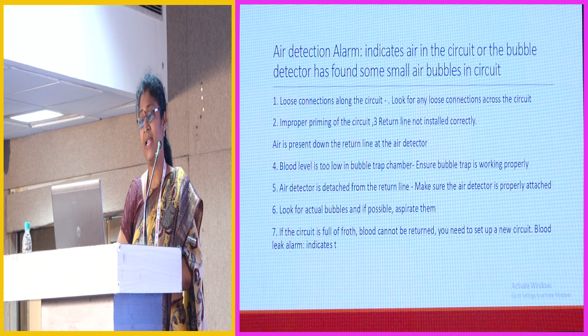So this is the blood leak alarm. The words are really nice, so I tried to paste the same. It indicates that the blood detector in the effluent line has found either blood or something it thinks is blood. So a blood leak alarm is not always blood. A ruptured filter membrane can cause a leak of blood, and you can see the ultrafiltrate is colored before you get the blood leak alarm. Or sometimes you can have severe hemolysis. And a recent dose of hydroxocobalamin injections, or methylcobalamin injections or something they get, causes discoloration of the body fluids. Sometimes the patient is on ATT, and of late we see most of these patients, which also causes discoloration of the body fluids.